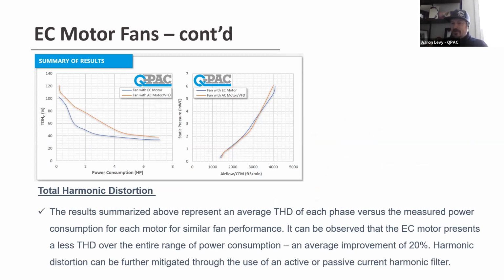One of the big misconceptions that I get a lot from contractors and from our competition is that harmonic distortion from a VFD setup to an EC fan is worse, and it's just not true. In essence, they're both 6-pulse inverters in the way that they deal with the harmonics. There are a few additional filters built into the electronics of an EC fan that give it anywhere from about 10 to 20% better harmonic distortion. But in essence, it's still roughly about the same.